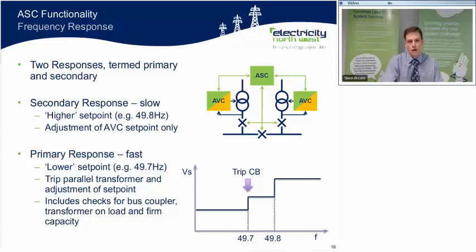Of course, we need to carry out some checks before we do this. We need to ensure that the two transformers are in parallel. So we check the bus section breaker, and also that both transformers are on load. And we also need to make sure that the firm capacity is such that we can take the load of the substation on a single transformer.